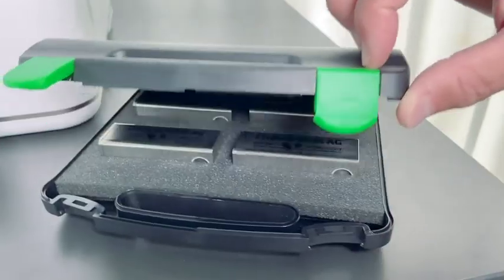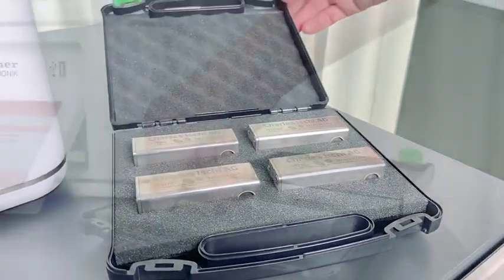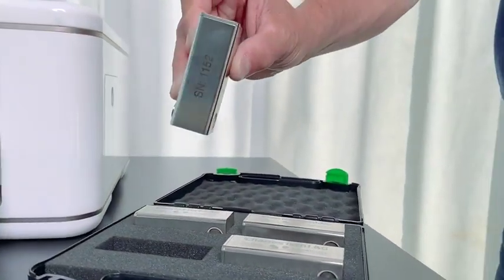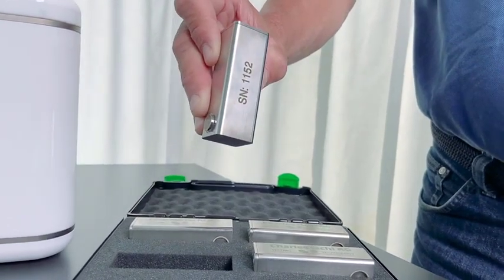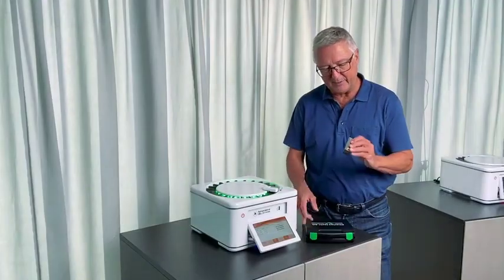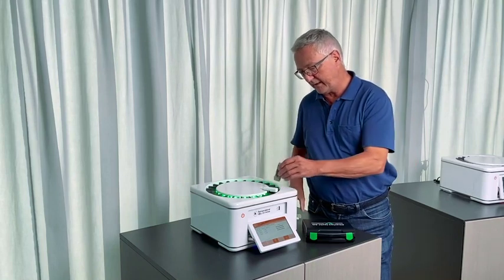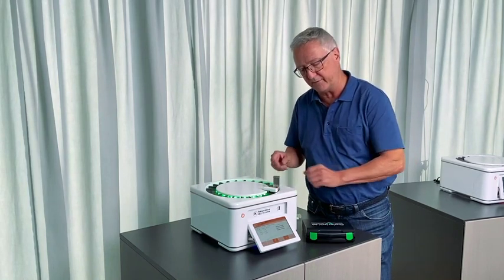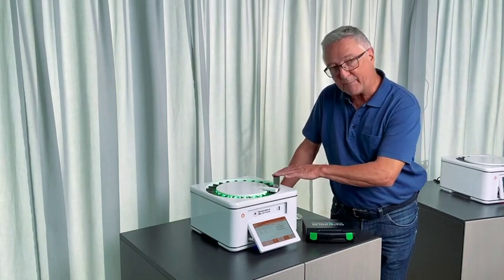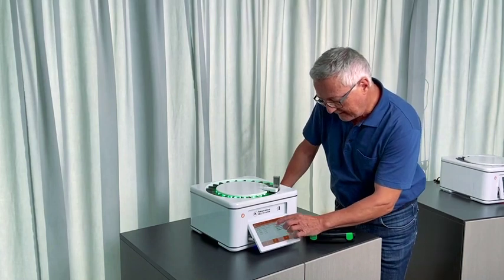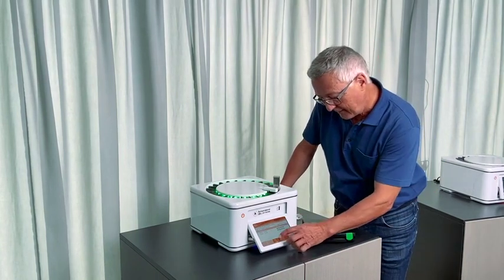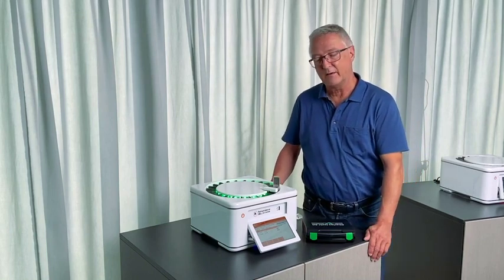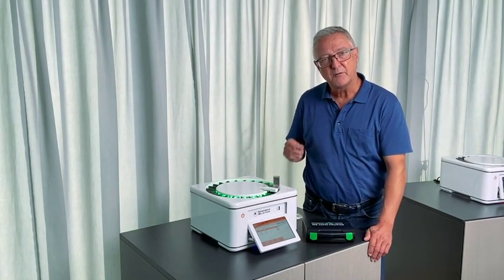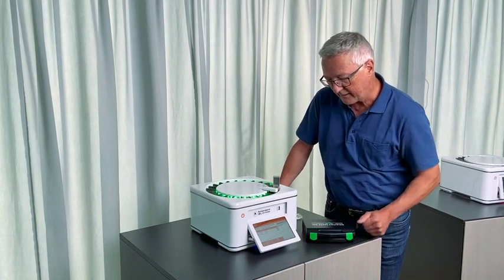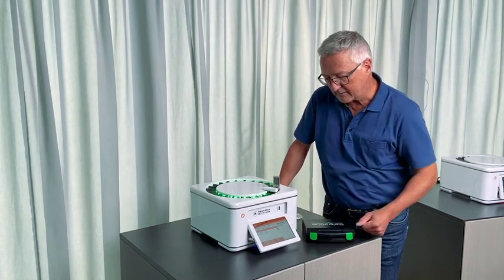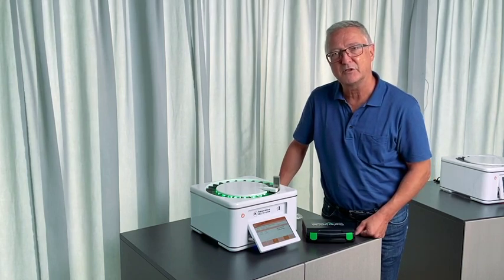For the daily calibration check of the hardness tester, we have a nice option. This is our mechanical tablet, a set of 4 different tablets in the range of 50, 100, 150 and 200 Newton. This tablet can be used to make a quick verification check if the hardness tester is working within the range. For this you can put the tablet into the hardness station and select the calibration mode and perform a measurement. The hardness tester will drive forward, make one measurement and give us a result which needs to be within a certain tolerance and which approves the accuracy of the tester.